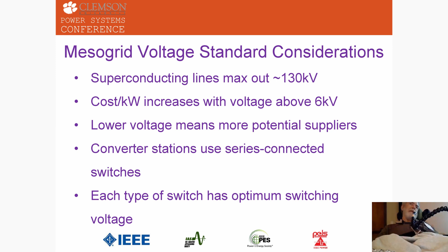I think all those other things are pretty obvious to you folks. Anyway, for any type of switch in that range of say around 120 kV, you're going to have series connected switches. If it's silicon, it's 6,000 volts per step. If it's thyristors, it's 8,000. If it's silicon carbide transistors, it's 15,000. So I think it's important to pick a standard voltage which is evenly divisible by many steps.